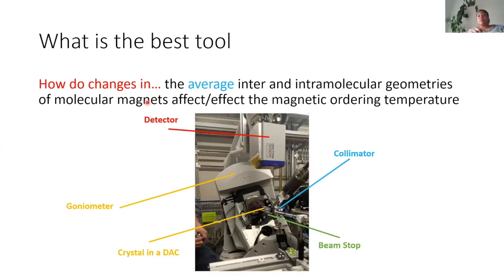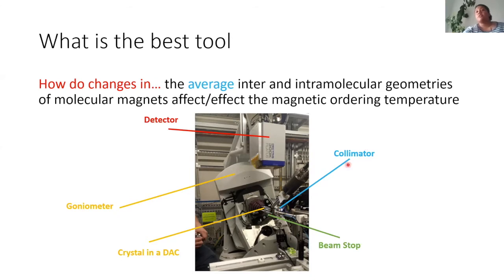At Diamond, specifically on I-19, a high pressure collection takes 14 minutes - almost the same amount of time to center the crystal and clear the experimental hutch as to take the actual measurement. The I-19 setup has a detector, a goniometer weighing about 70 kilos, and a much finer collimated beam. You can select the wavelength you're interested in and the beam is much brighter. Instead of a frame taking 5 to 60 seconds, it takes about 0.04 seconds per frame.